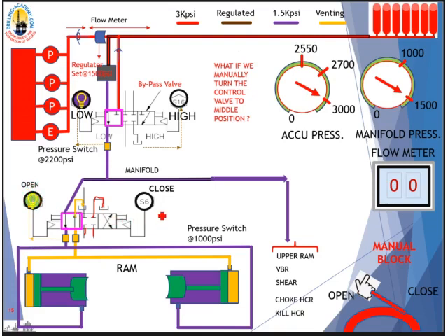All right. Now, if I go down to the local Koomey unit, I grab the valve handle and I turn it to the middle position. There is no air acting on both sides, right? So the valve is manually moved from open to middle position. Nothing changes to the lines in here, right? Because internally inside the valve, all the ports are blocked. Therefore, the open line still retains the pressure in it, 1500 psi. And the pressure switch here still senses that value and sends the signal to light up the open light pop.